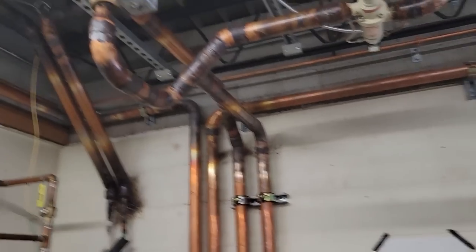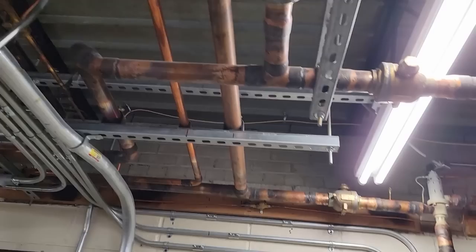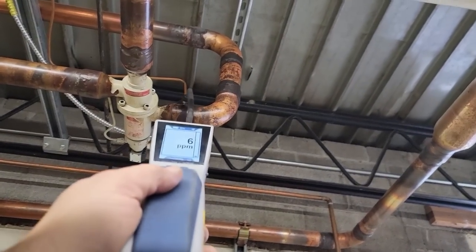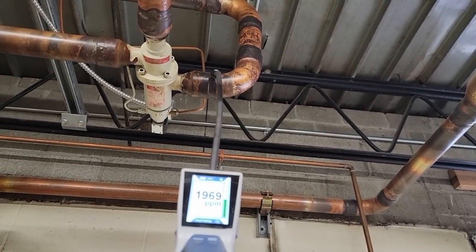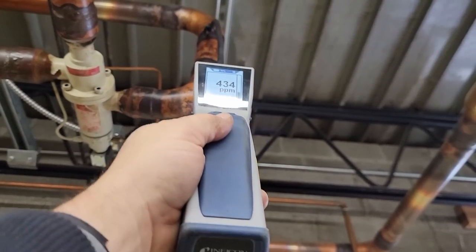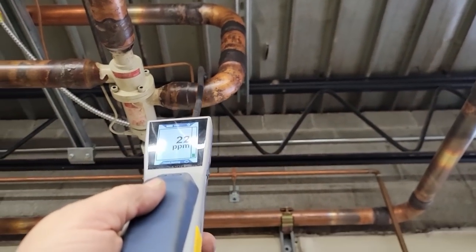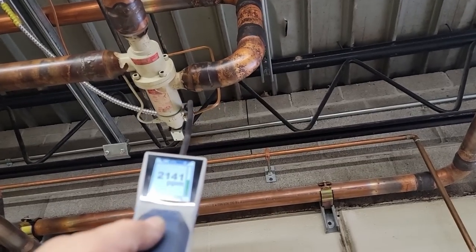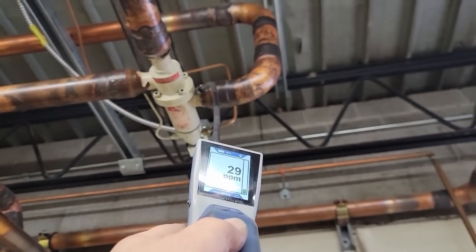All right, well, following the discharge line, which is hot gas, over to here in sniffer mode. All of a sudden I narrowed it down, put it in parts per million. We got a leak. It's definitely on that fitting down low. You can see it's dropping. Come back down, boom. Hopefully it's one of these flare fittings. That'd be awesome. But it just does not like